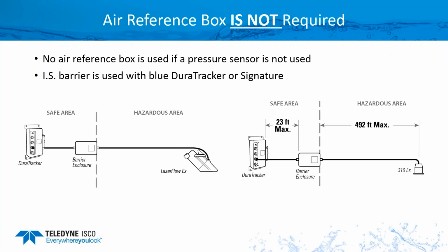Now, applications where the barrier or air reference box is not required is when the pressure transducer is not in use. With an ultrasonic or the non-contact laser flow sensor, they're not using the pressure transducer, so no need for that box. Order the longer cable length, go into the safe area, install the barrier box, and go directly into your controller.